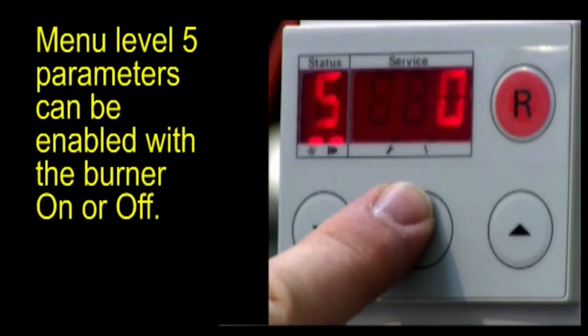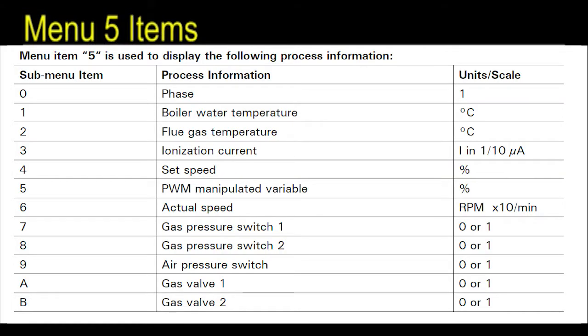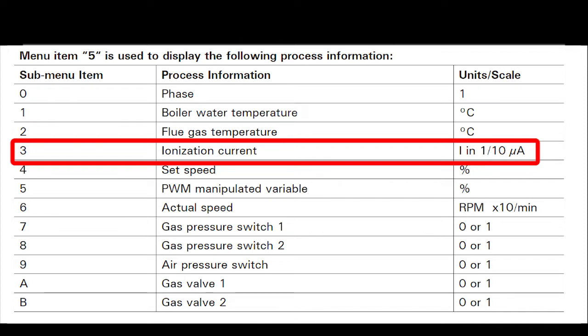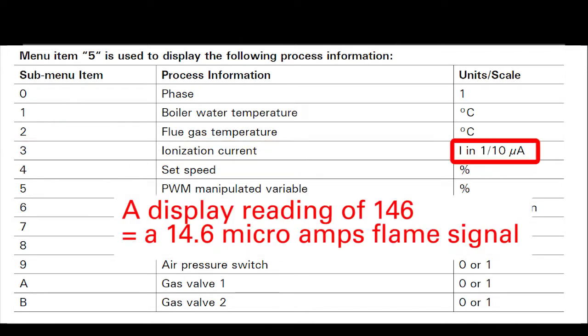All menu level 5 parameters can be enabled with the burner on or off. Flame signal is located in the menu 5 level. A chart of the level 5 menu items can be found in the CM2 service manual. Flame signal can be checked at submenu level 3. At a 1/10 microamp resolution, a displayed signal of 146 represents 14.6 microamps.